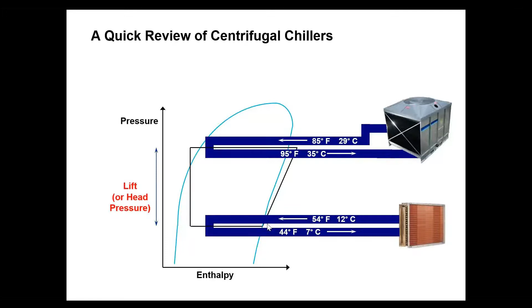Now the term that I mentioned in this slide is called the lift. Lift is the amount of work done by a centrifugal compressor. So when you talk about lift or head pressure, it is the work done by the compressor. That means the pressure being imparted by the impeller onto the refrigerant for it to go from a low pressure refrigerant to a high pressure situation. So you are actually changing the pressure of the refrigerant because you are imparting tangential velocity and converting the kinetic energy into pressure energy. Lift, if you see on your left, is denoted in red. That means the entire compression process is a process by which you convert the low pressure refrigerant into a high pressure refrigerant, and that is done by imparting tangential velocity on the refrigerant.